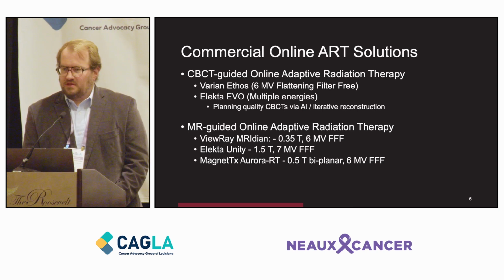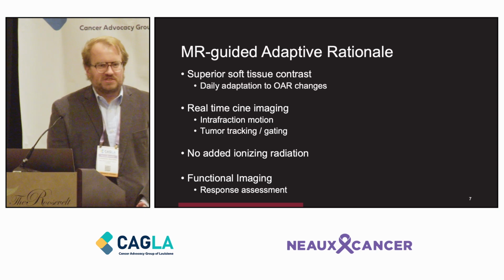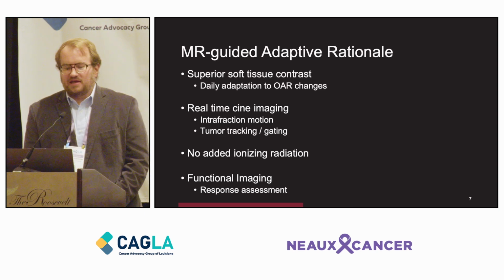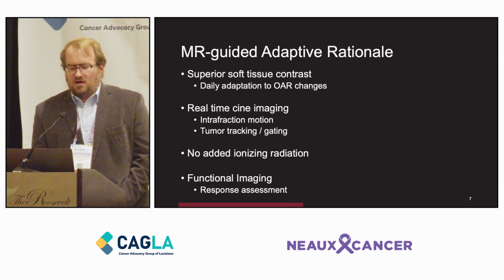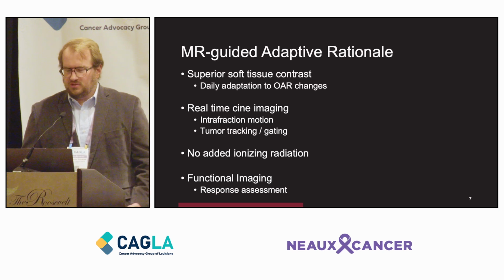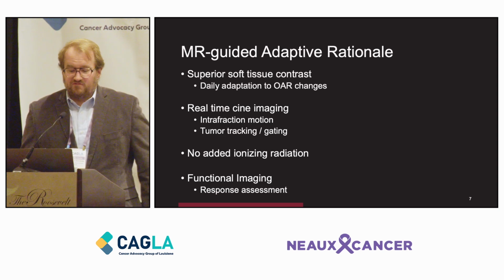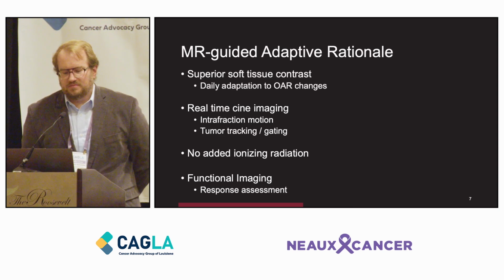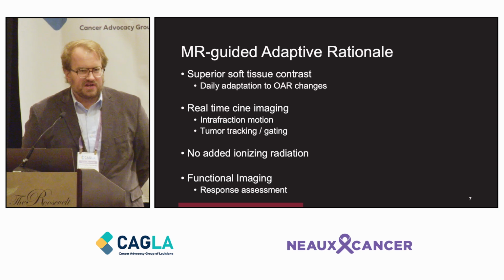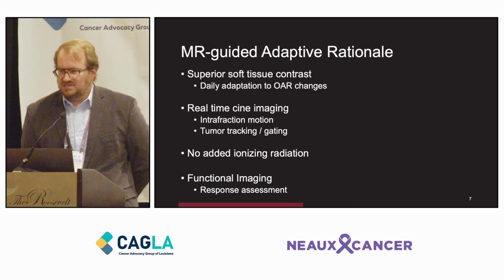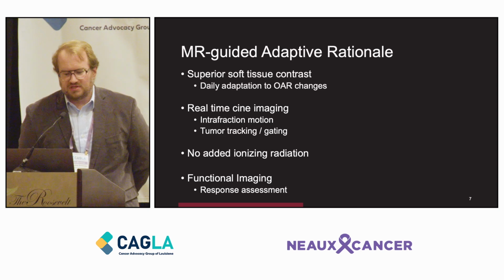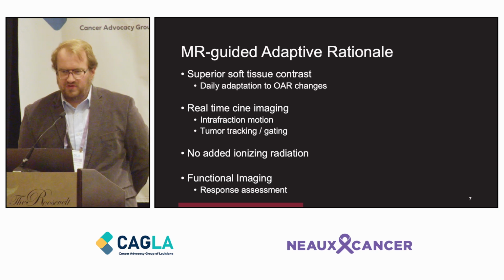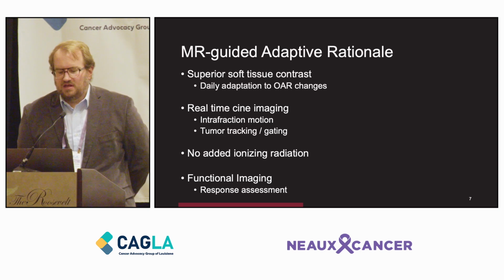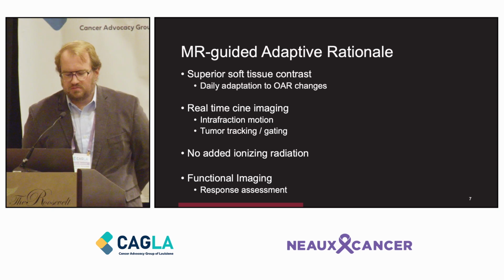But sort of the other side of the coin of online adaptive radiation therapy is MRI-guided adaptive radiation therapy. And there are a few competitors in this market, two major ones and one that's sort of an upstart. ViewRay is a company that started specifically making an MRI-guided radiation therapy device. Initially, it was a cobalt-60 unit that used cobalt-60 as the source of its radiation, but then they switched to their MRIdian, which is a low-field MRI, so a 0.35 Tesla scanner, and it has a 6 MV, 6 megavolt, flattening filter-free linac that produces a 6 MV FFF radiation beam.